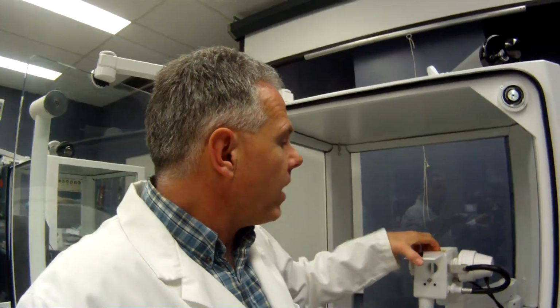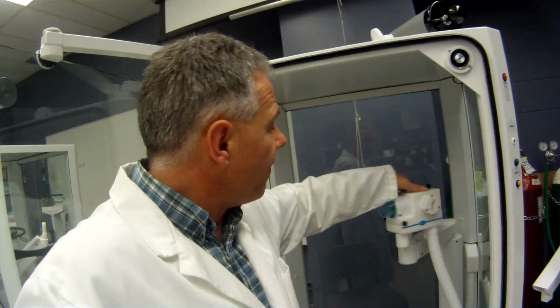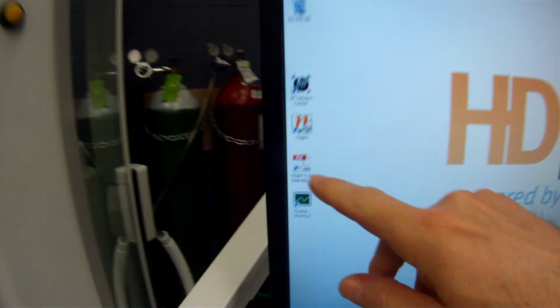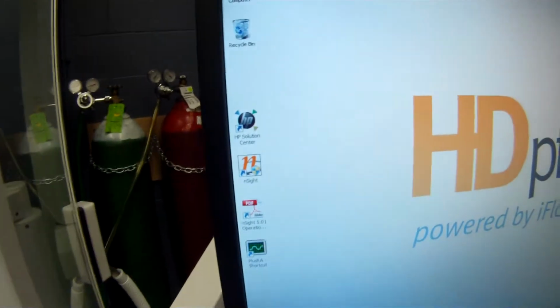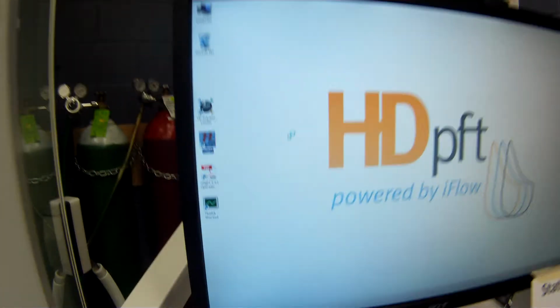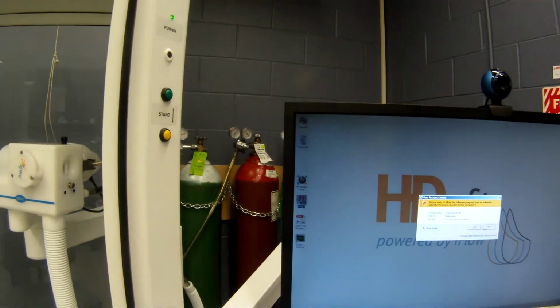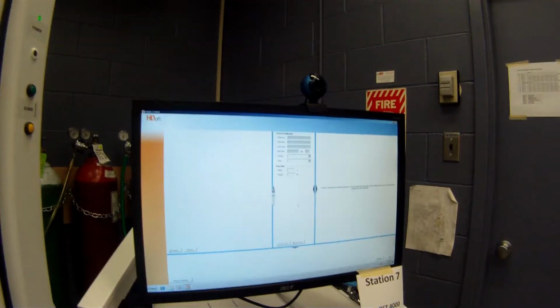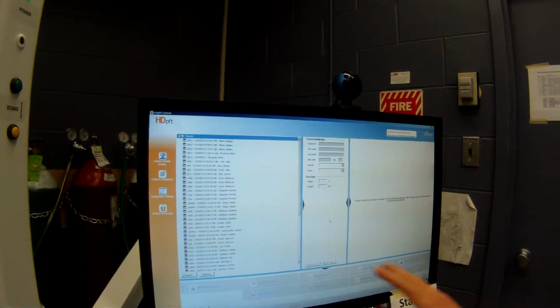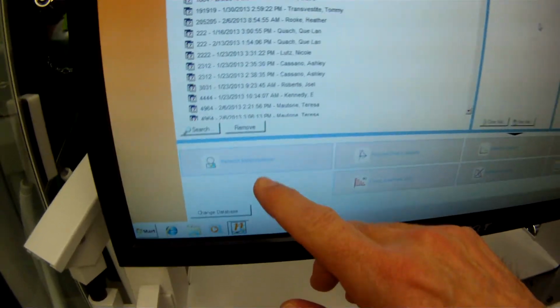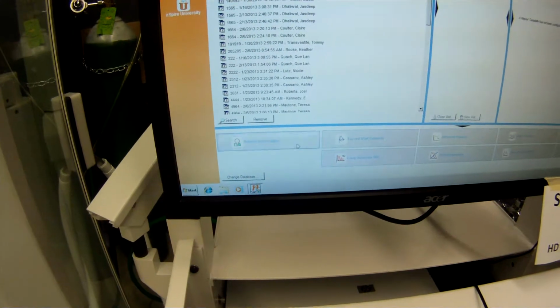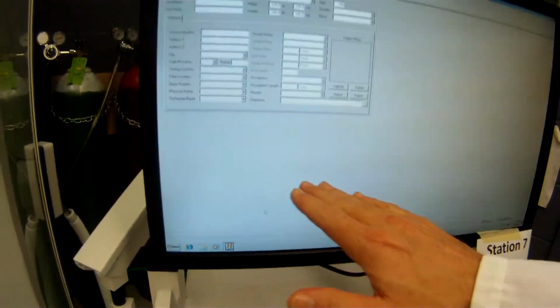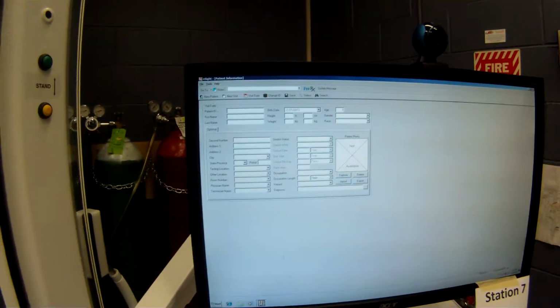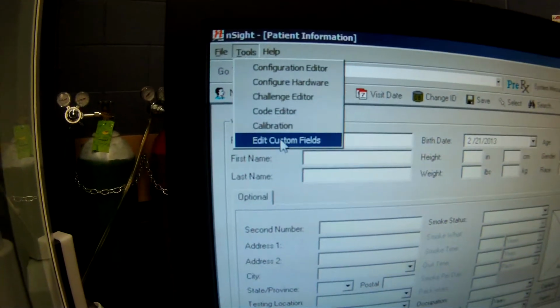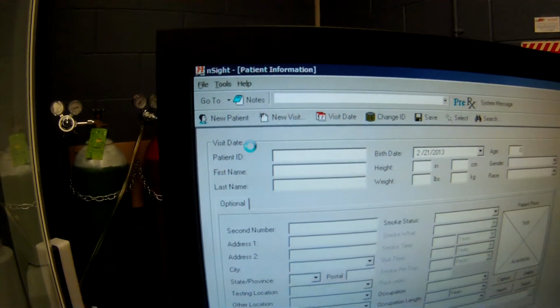All right. So we're going to show you how to do a calibration of the basic pneumotach here. So let's go get orientated to the software. We're going to use the nSight software to do this. Now initially it opens up with the patient access screen here. What we need to do is go into the patient information, just because we're going to do a calibration. This is the screen we would use to input new patient data. Go up to tools up here, and we're going to calibrate this device.